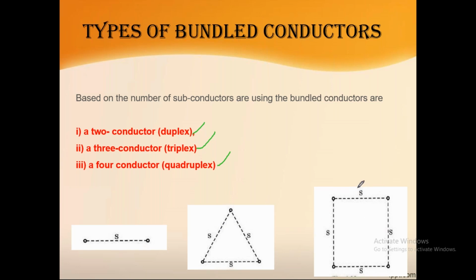At the same time, here S represents the distance between the 2 subconductors. And how can we measure the distances? Suppose these 2 are subconductors, and this, so these are the 4 subconductors. If you want to calculate the distance between these, you have to calculate the distance between the 2 conductors from the center point of view. So from the center of this conductor to the center of this conductor, only then can you calculate the distance between them. So this is the way of calculating the distance from the center of each conductor. Here to here, this is D. From here to here, this is D, and here to here. You should not calculate like this. From center to center, it is called the distance between the 2 conductors. So that is the way we are placing the conductors.